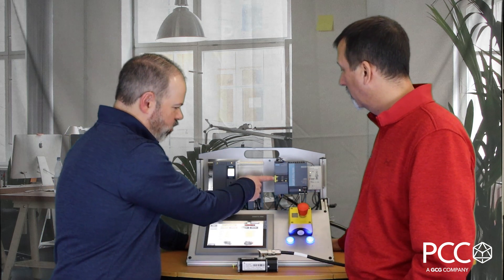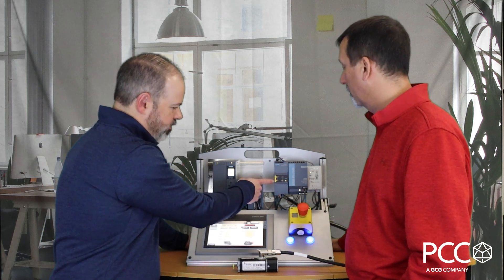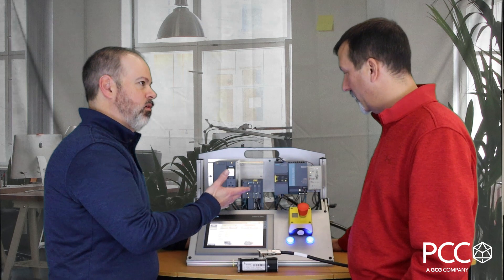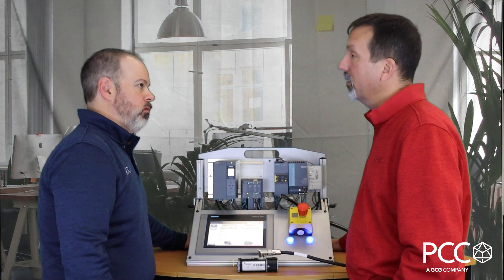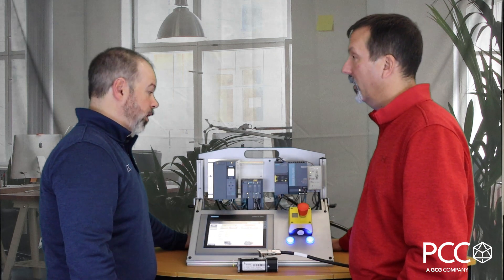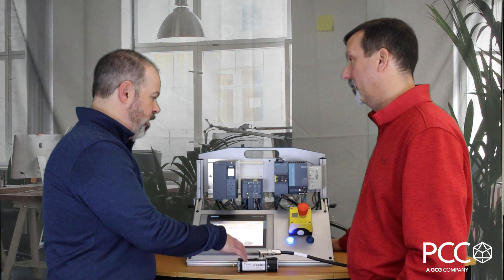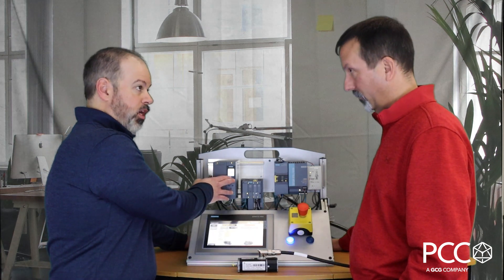So I see there's yellow on this micro drive, does that have safety included? Yep there's a safe fail safe version, the F version. Okay so you can buy it with safety or without safety. That's correct. And obviously you can control the safe torque off of the motor then through PLC based communications over Profinet. If it's a safety PLC, correct.